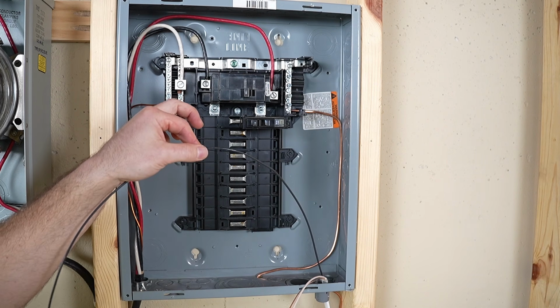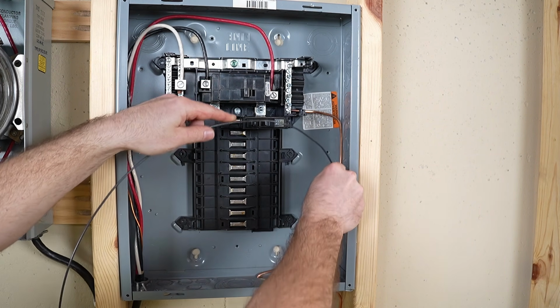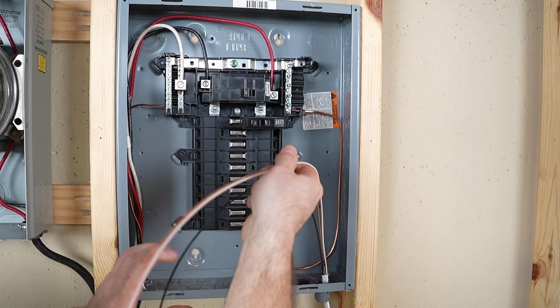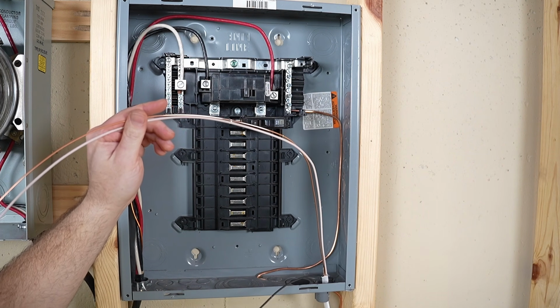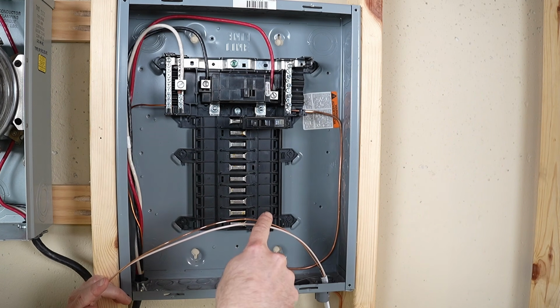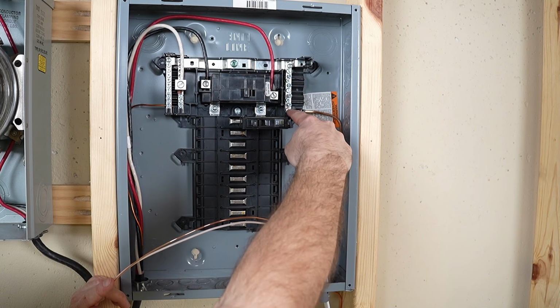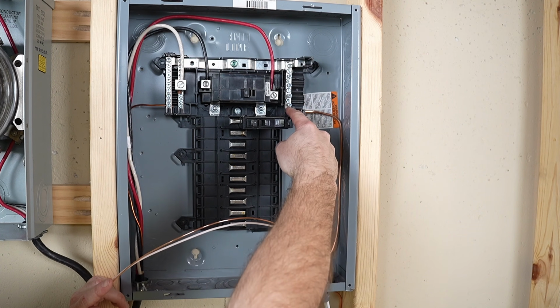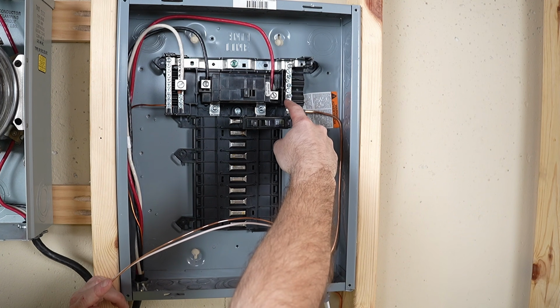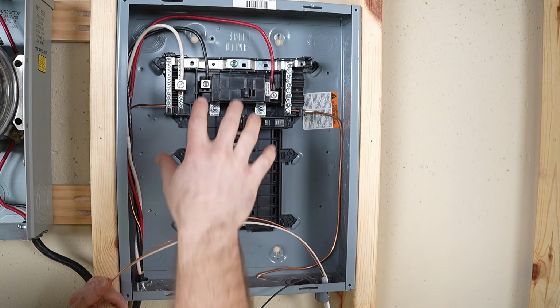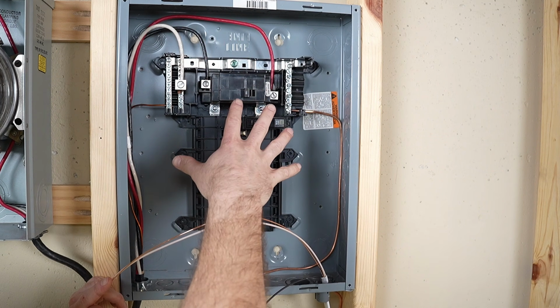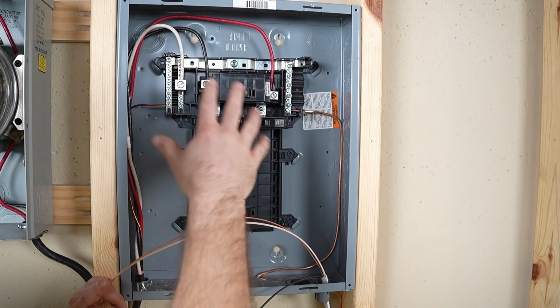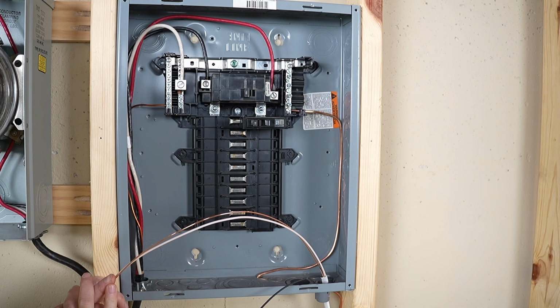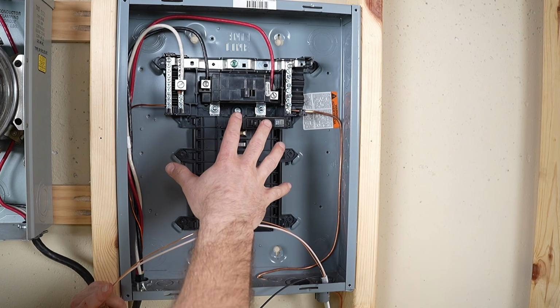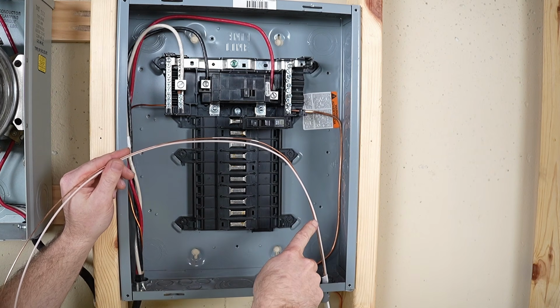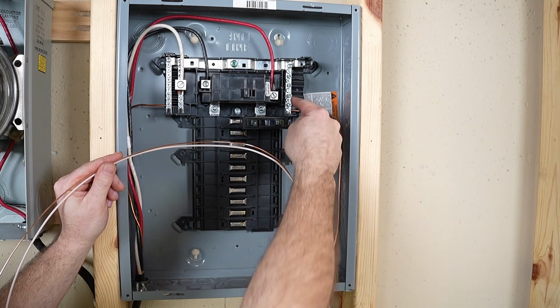The black wire, the hot wire, goes to our circuit breaker. But where do we bring the other two wires, the neutral and the ground? Because this is a main electrical panel, we can share the neutral bus bar. The ground and the neutral can both land on this bus bar. If this were a sub panel, we'd have to separate the ground and the neutral, but that's a topic for a future video. So because this is a main electrical panel, we're going to share the neutral and the ground at this bus bar.